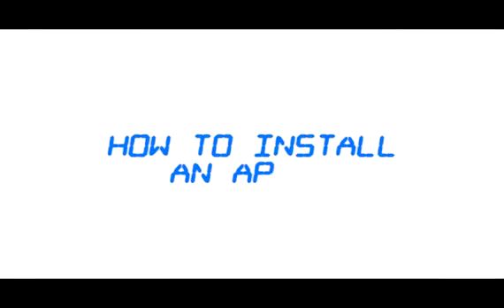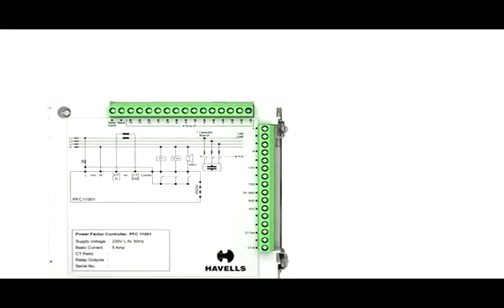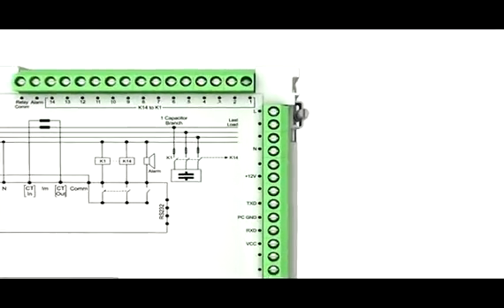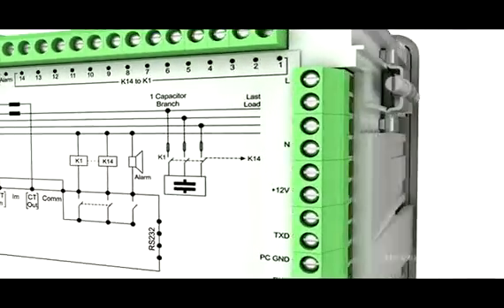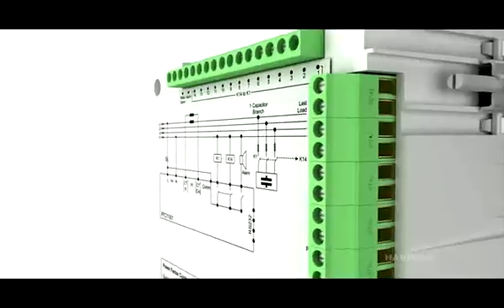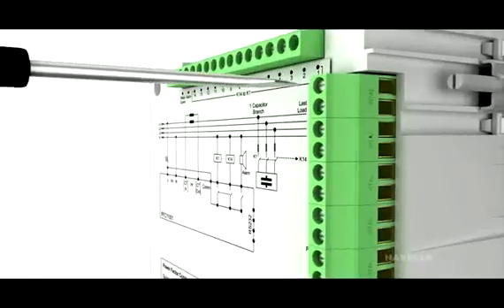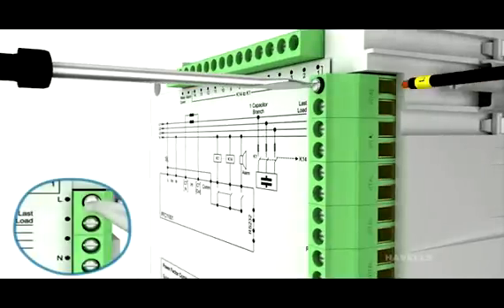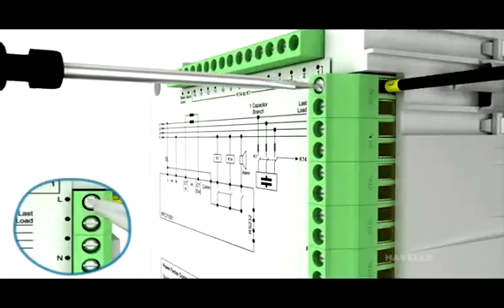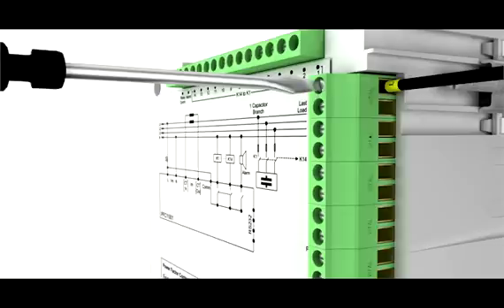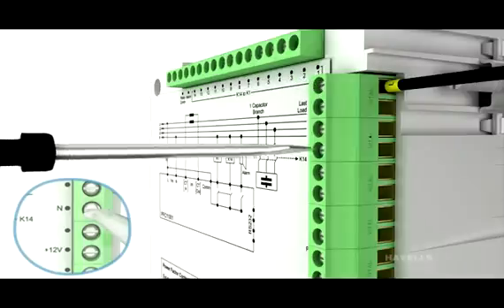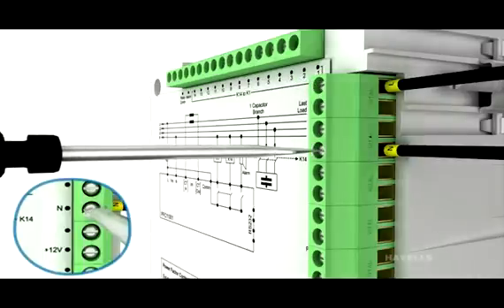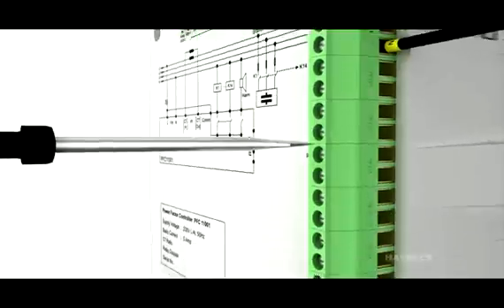How to install an APFC? Firstly, connect any of the phases R, Y or B to the L terminal of the connector. For protection, use a 2 ampere fuse or MCB also in the circuit. Connect neutral to the N terminal of connector.